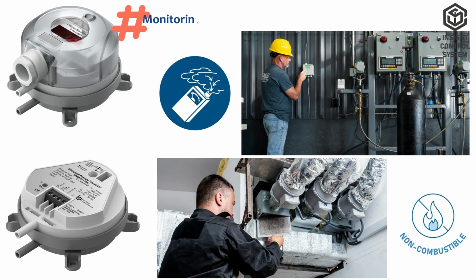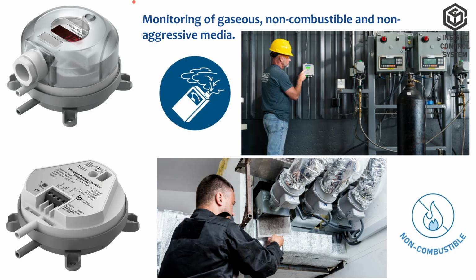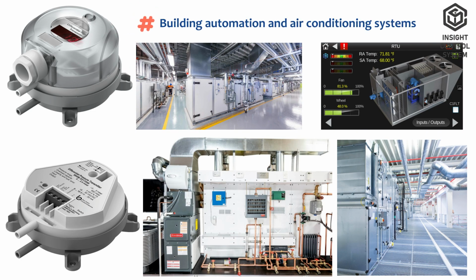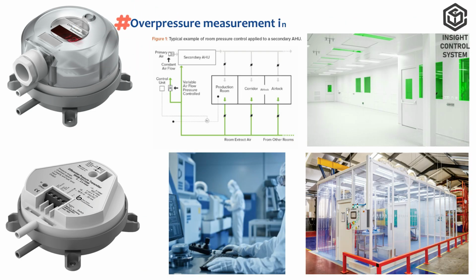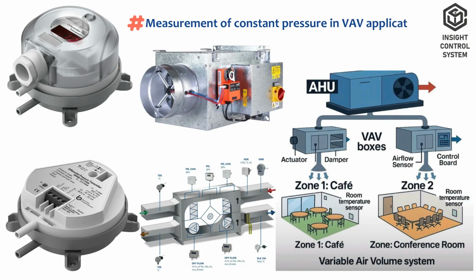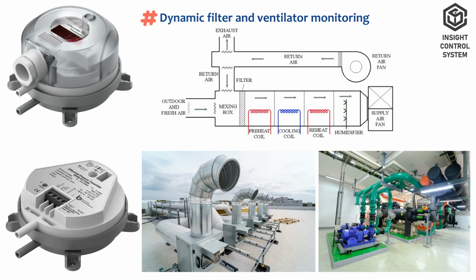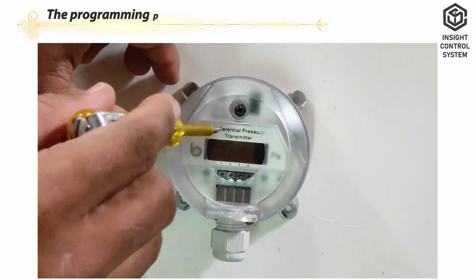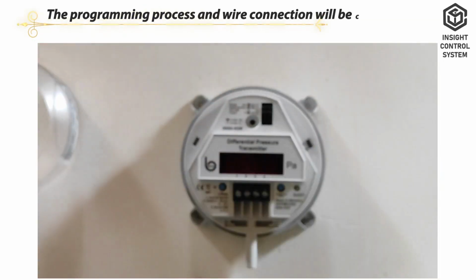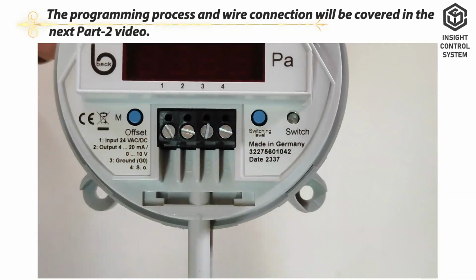Applications. Monitoring of gaseous, non-combustible and non-aggressive media. Building automation and air conditioning systems. Overpressure measurement in clean rooms and laboratories. Measurement of constant pressure in VAV applications. Dynamic filter and ventilator monitoring. The programming process and wire connection will be covered in the next Part 2 video.